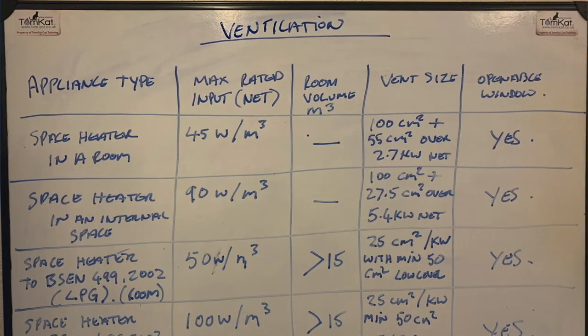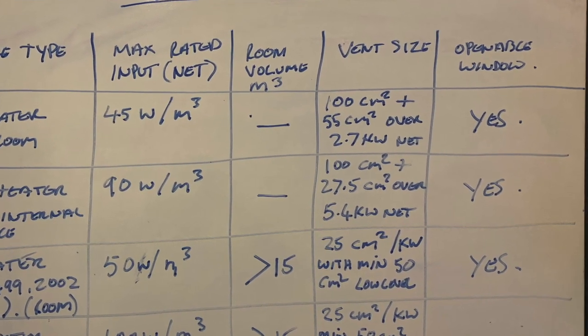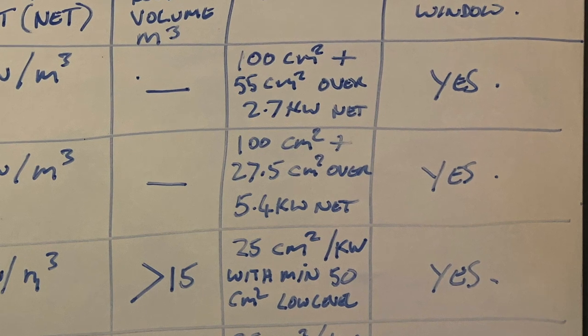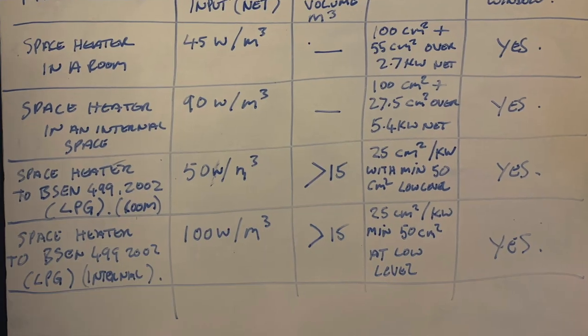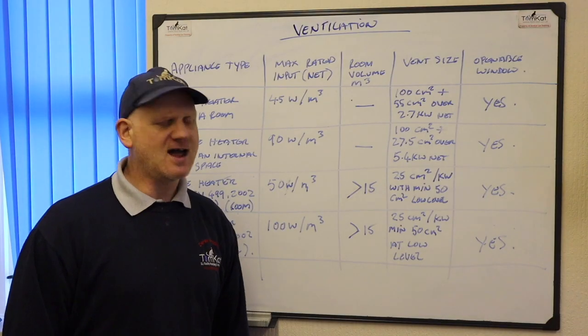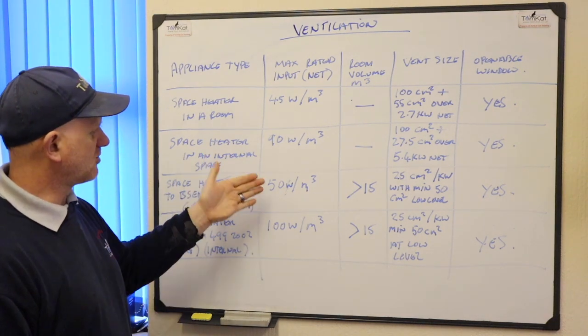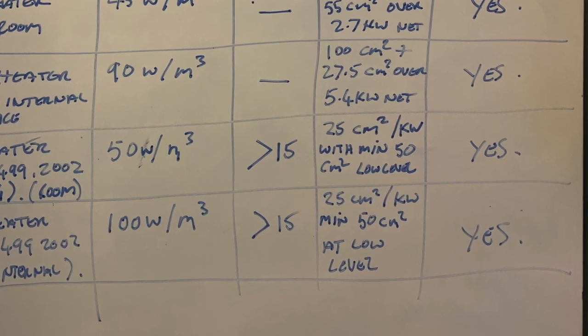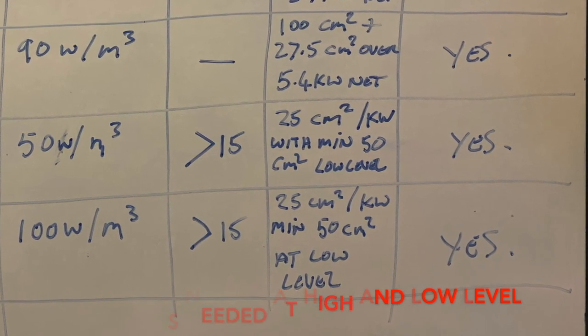For a space heater in an internal space it's 90 watts per metres cubed, and the vent required is 100 centimetres squared plus 27.5 centimetres squared for every kilowatt over 5.4 kilowatts net, with an openable window. For a space heater conforming to BS EN 499:2002 — which is an LPG fire stored in a room — it's up to 50 watts per metres cubed, the room volume must be greater than 15 metres cubed, and the vent is 25 centimetres squared per kilowatt with a minimum of 50 centimetres squared at high and low level, plus an openable window.